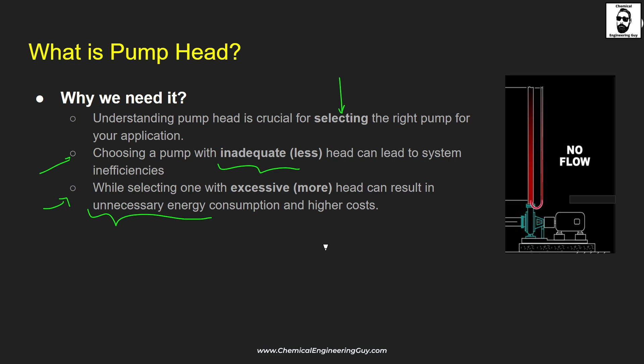On the other hand, if you choose a pump with a lot of excess head, you're going to have excess, as the name implies. But this will result in unnecessary energy consumption. You're going to have higher costs. You will need to increase the friction of your system in order to account for the given flow rate and pump power. And last but not least, guys, why do we prefer to state pump head rather than pump pressure?